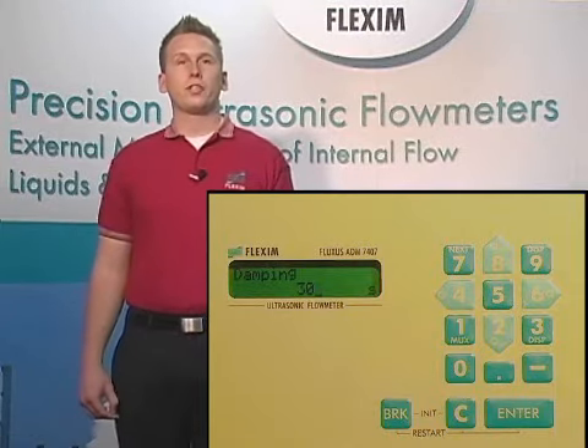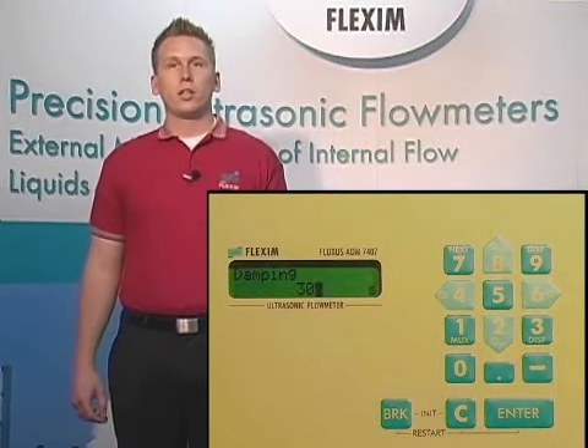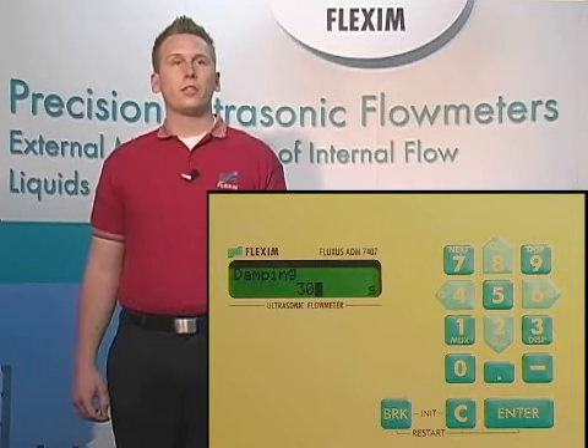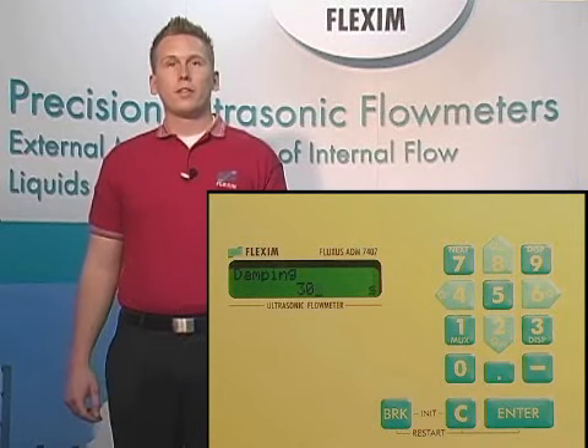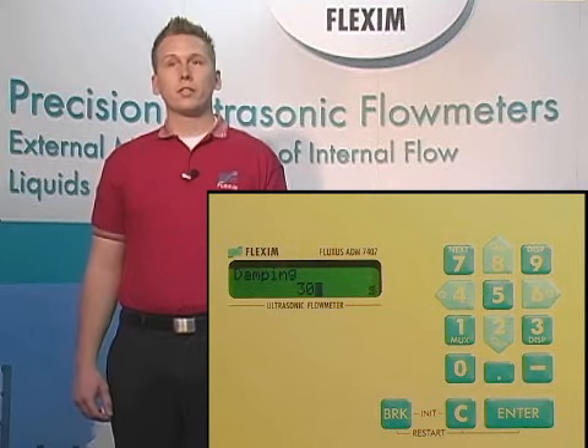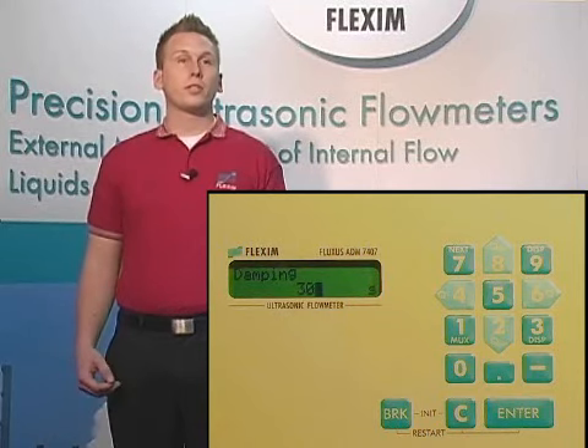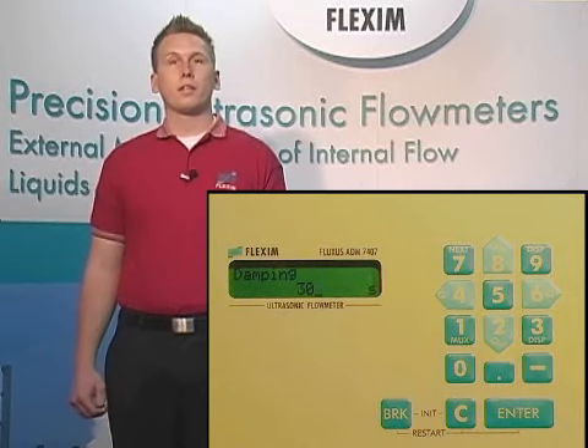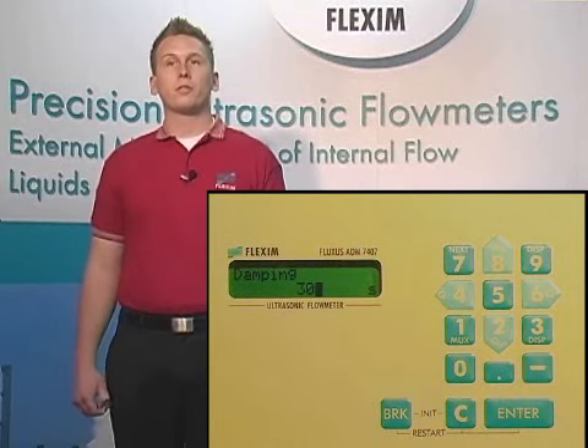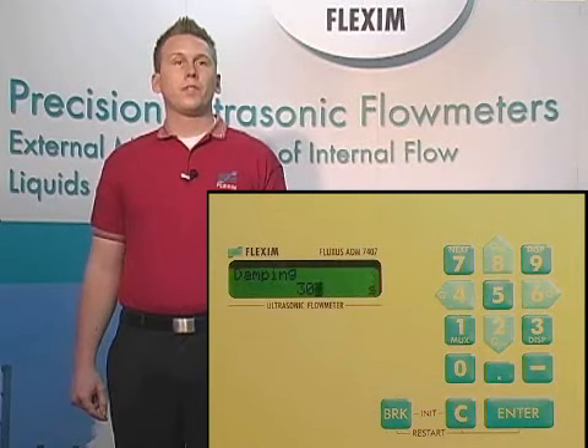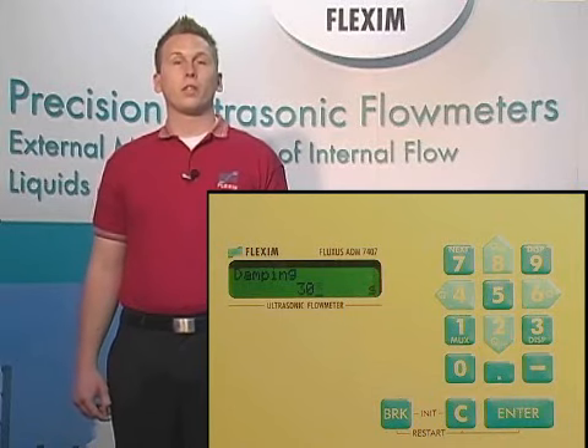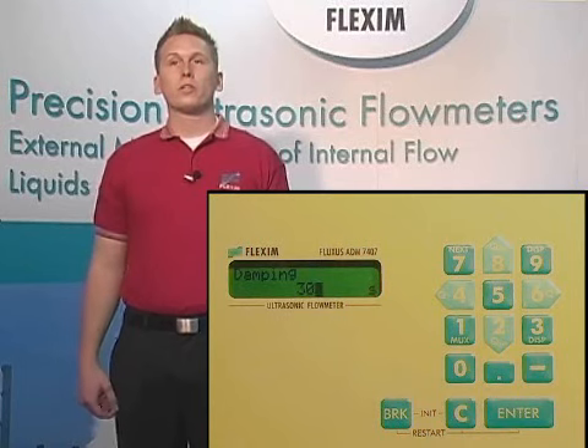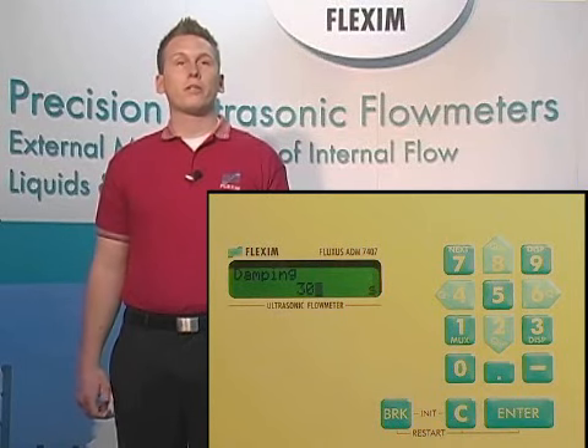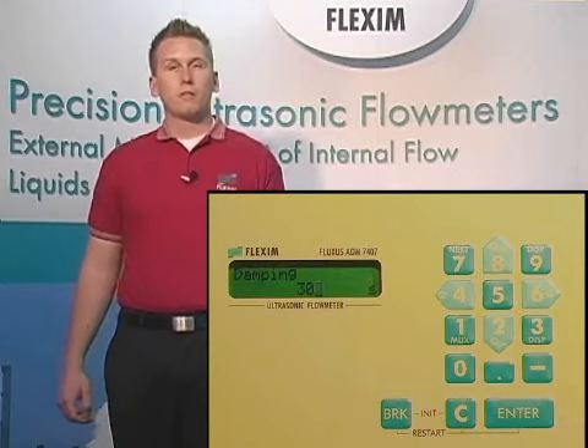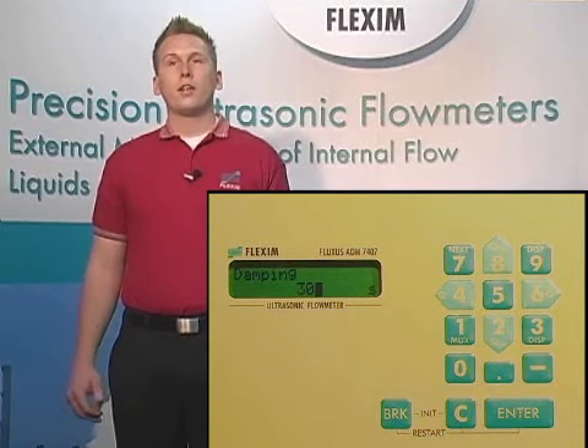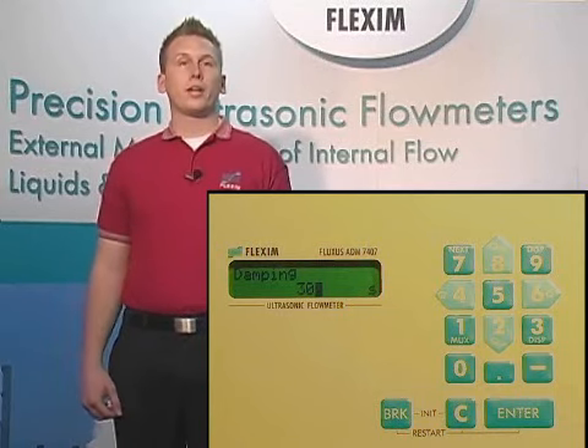Dampening is the amount of averaging the meter will perform while measuring. For example, we generally use 30 seconds of dampening for our measurements. This means that the meter will average 30 seconds of flow data, and every subsequent second the meter will take in 1 additional second of data and throw out data from 31 seconds previous. This way we're always looking at the average flow rate over the last 30 seconds. Of course, if you like to average over a shorter or longer period of time, this is perfectly fine as well. For now though, let's use 30 seconds. And since this is already in the meter, we can simply hit enter to confirm.